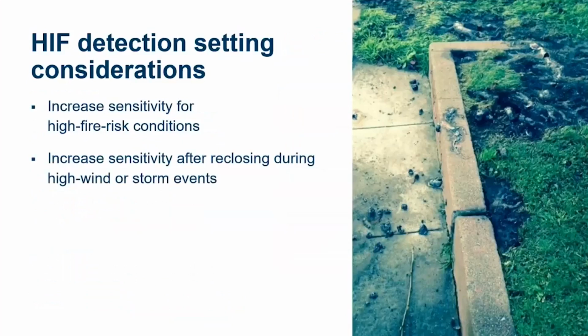One of the ways this can be used is if we know we have an elevated fire risk. Maybe looking at the weather data, we know we're going to have a red flag day. Potentially, we may want to manually assert that, or maybe we have some automated logic to set a latch to assert our high sensitivity mode. It could be that we want to increase sensitivity after reclosing in conditions where we have high wind events or storm events.